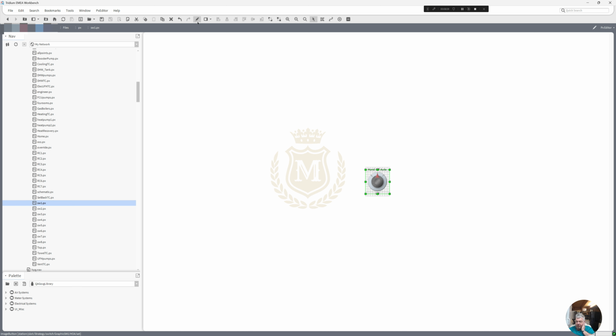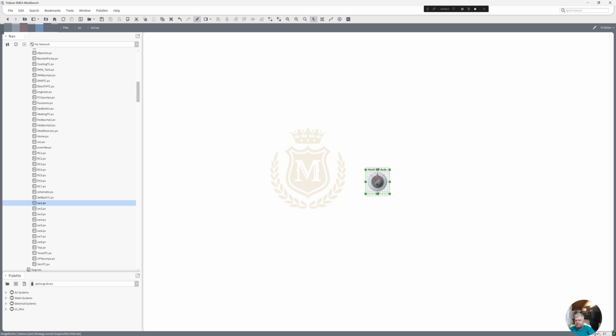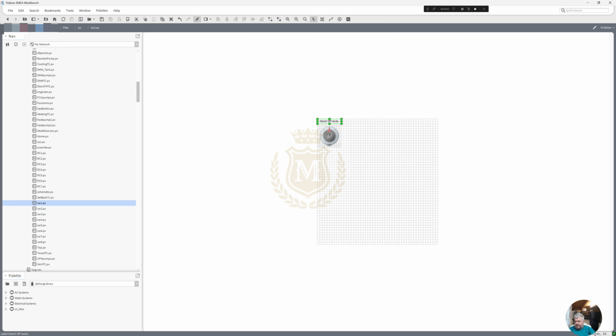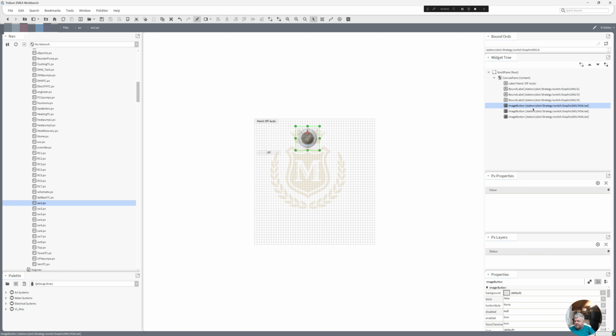So when we actually click on this switch, we get the auto, we get the hand, and we get the off. And the graphics for this, I think, is a standard palette, kit PX HVAC miscellaneous dial switch, middle position for that particular one, but layered on top of each other. If I move this lot around and I edit the properties, and let's put this to a larger size. Let's put that to 500 and that to 500 and move that back. I could take that there and we'll bring in this side piece here, and that is one that's invisible at the moment, and that's the other one that's invisible at the moment. That's the only one that's actually shown.